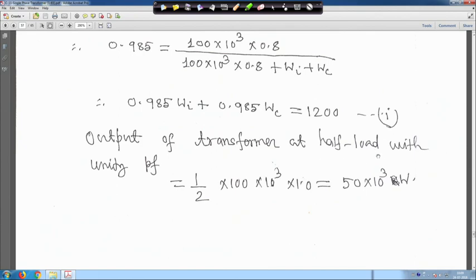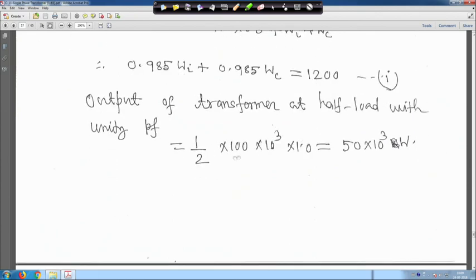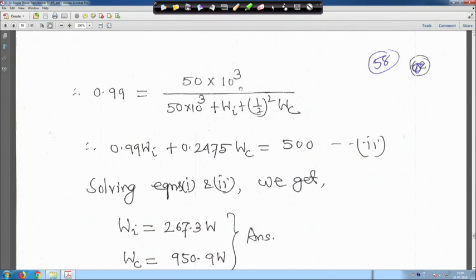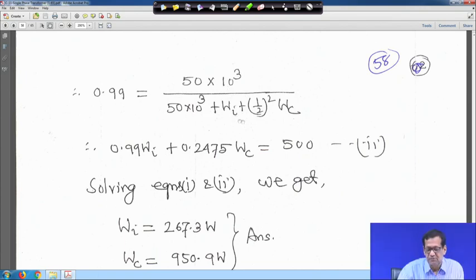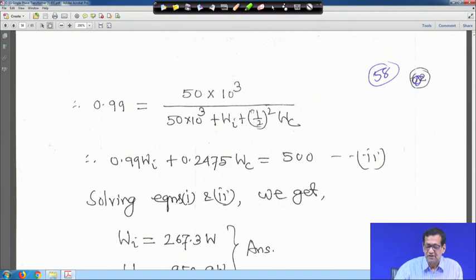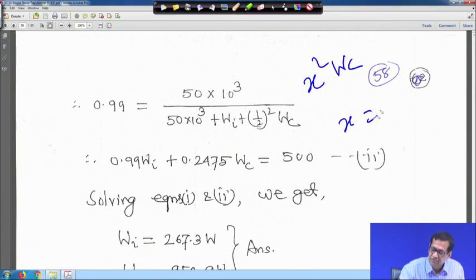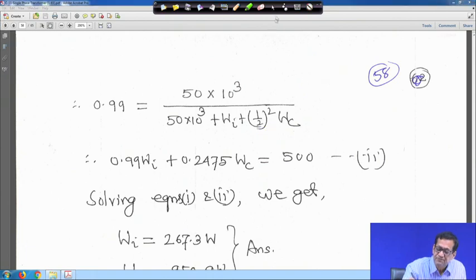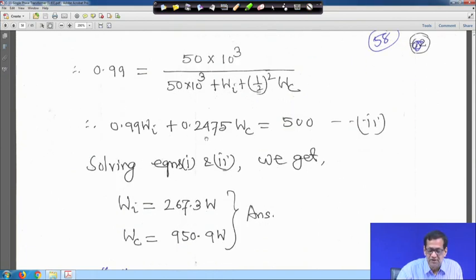At half load with unity power factor, output is 50 into 10³ watts. Efficiency is 99 percent, so 0.99 equals 50×10³ divided by 50×10³ plus W_i plus (half)² W_c. Since x equals half, the copper loss term is x² W_c = 0.25 W_c. After simplification: 0.99 W_i plus 0.2475 W_c equals 500. This is equation 2.